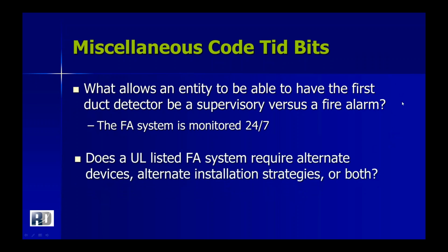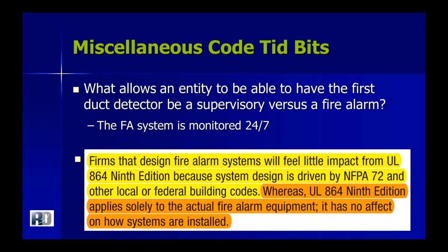Does a UL-listed fire alarm system require alternate devices, alternate installation strategies, or both? Next. So the answer is alternate devices. And if you click there, where we're going is kind of from the UL 864, where that is actually really just applying to the actual pieces of fire alarm equipment, the components themselves. It doesn't dig into how the systems are actually installed.